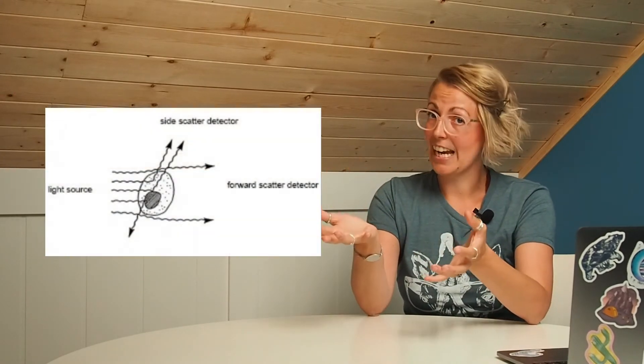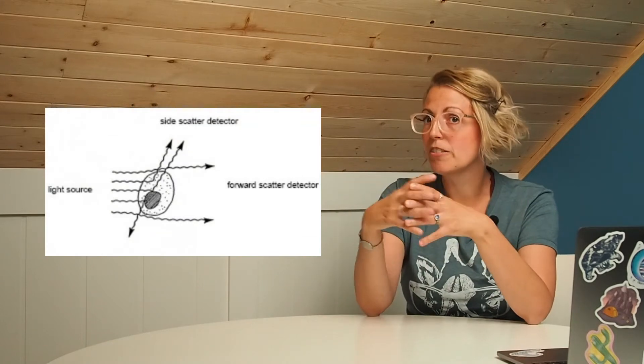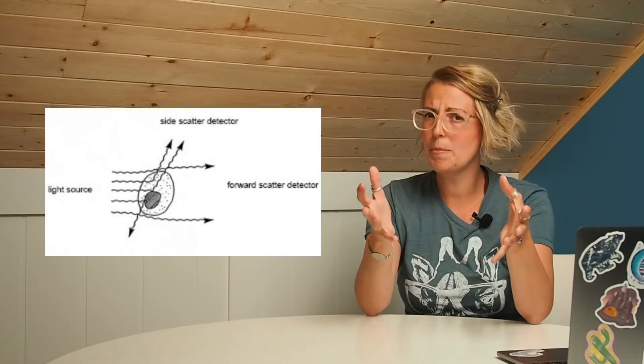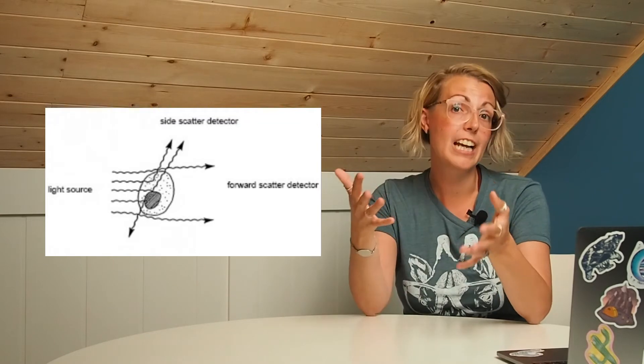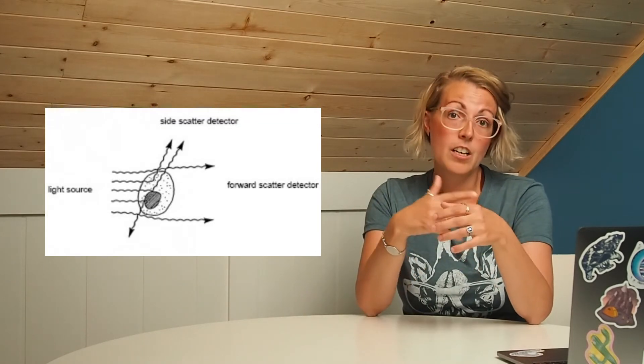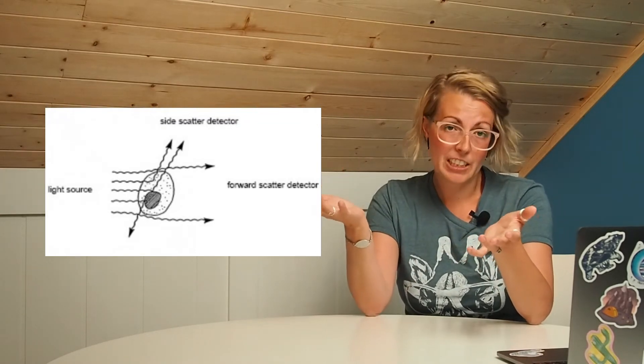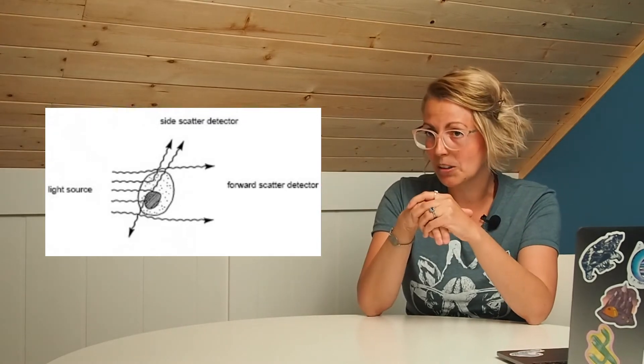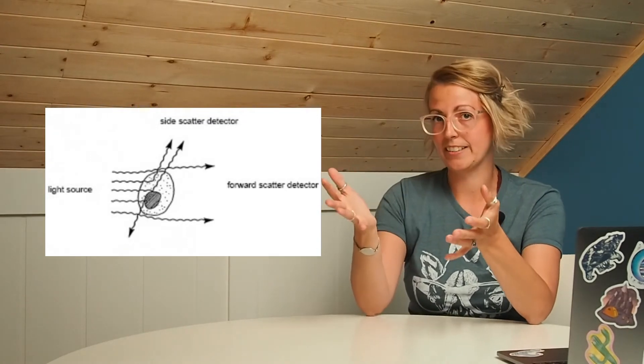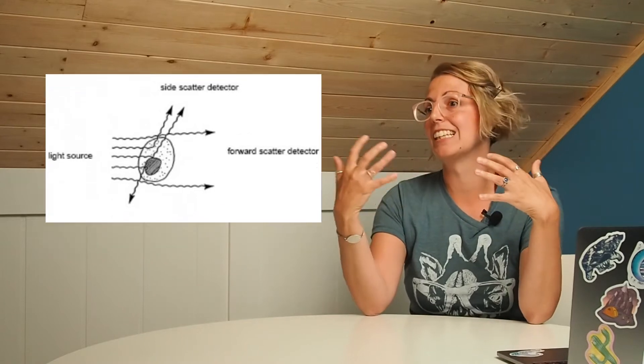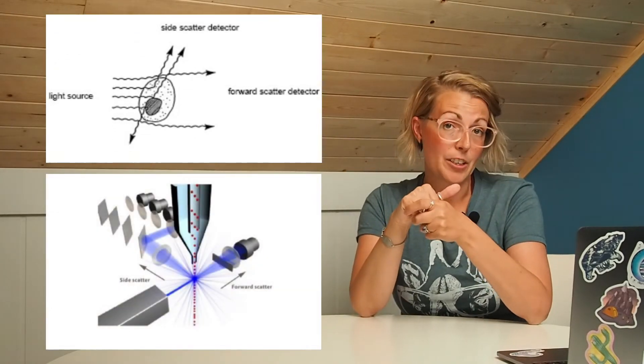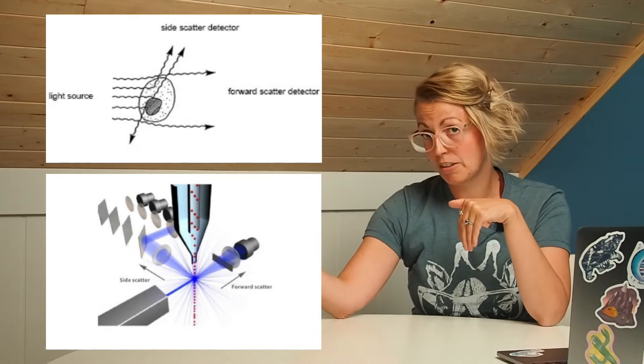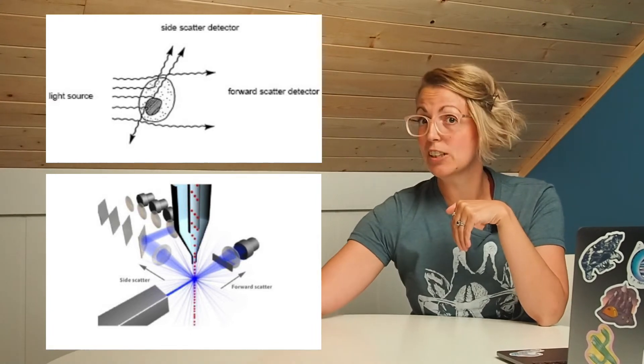Thinking about light scatter, this is where you've probably heard of forward scatter and side scatter. These are the two major properties of cells that we look at with our light scatter. Now forward scatter is classically referred to as the size of a particle. However this is not always the case. It's really a measurement of the diffracted light. It's called forward scatter because the detector is at a forward angle from the light source, so directly across.